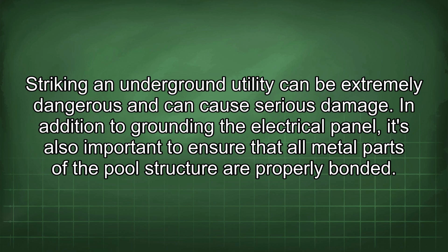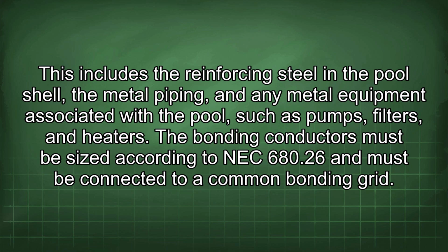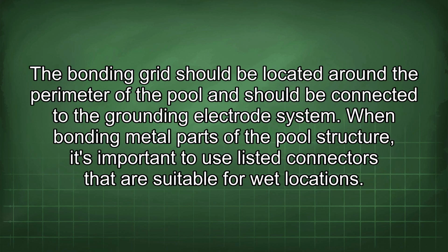In addition to grounding the electrical panel, it's also important to ensure that all metal parts of the pool structure are properly bonded. This includes the reinforcing steel in the pool shell, the metal piping, and any metal equipment associated with the pool, such as pumps, filters, and heaters. The bonding conductors must be sized according to NEC 680.26 and must be connected to a common bonding grid. The bonding grid should be located around the perimeter of the pool and should be connected to the grounding electrode system.